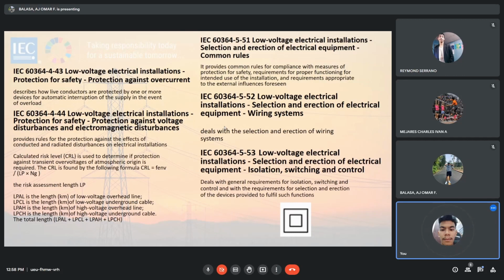60364 Part 552, Low Voltage Electrical Installations, Selection and Erection of Electrical Equipment. So, wiring systems naman. Deals with the selection and erection of wiring systems. Types of wiring systems: the method of installation of a wiring system in relation to the type of conductor or cable used shall be in accordance with Table 52.1, provided the external influences are covered by the requirements of the relevant product standards. The method of installation of a wiring system in relation to the situation concerned shall be in accordance with this standard. Examples of wiring systems together with reference to the appropriate table of current carrying capacity are in this standard.